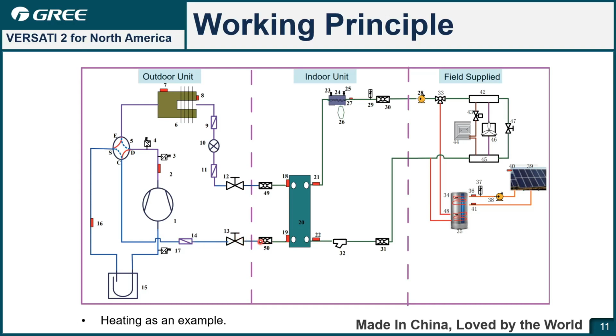This is the sensor to detect the temperature, and then the hot gas becomes liquid and flows to the expansion valve, and then flows to the outdoor unit for evaporation, and then flows back to the liquid gas separator, then flows back to the suction side. So that's the refrigerant circulation in the outdoor unit.